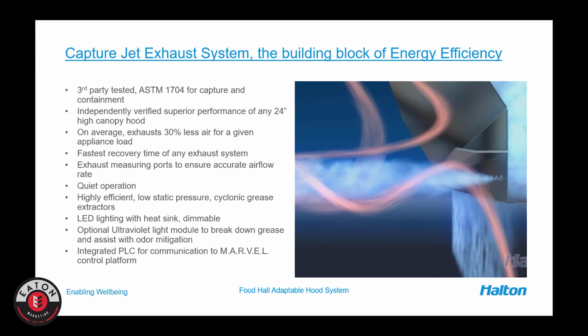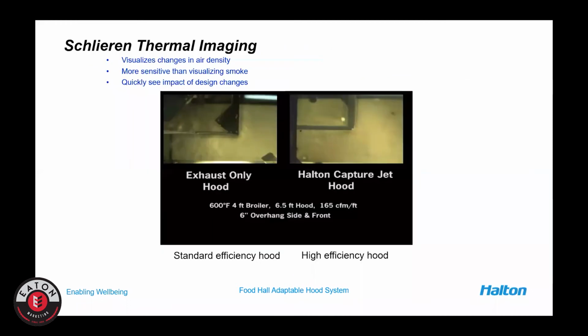So when we think about the energy for a typical hood system, the fan energy is a part of that, but the bigger part of it comes from the reduction in HVAC on the mechanical side. So if we're able to reduce air in the exhaust side, we can reduce tonnage on the HVAC, fan size, ductwork, and the associated energy that goes along with running that system. So Capture Jet is, here's just a quick video of two hoods side by side. The hood on the right is actually a Capture Jet hood, and we have those jets turned on. The hood on the left is a standard exhaust hood.